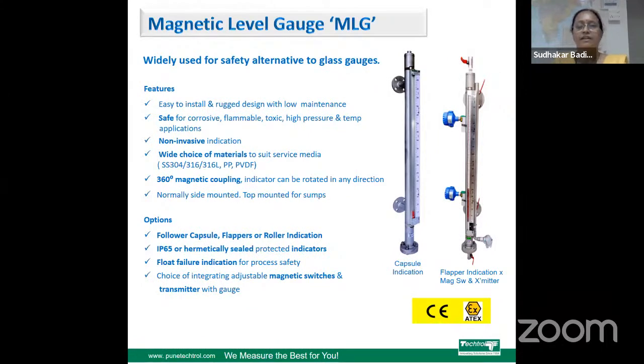So the next one is the magnetic level gauge, that is MLG. This gauge is widely used as a safety alternative to glass gauges. The gauge is very easy to install and has a very rugged design, hence it has low maintenance. It is safe for corrosive, flammable, toxic, and high pressure and temperature applications. The indicator is non-invasive as it is mounted or clamped on the chamber from the outside.